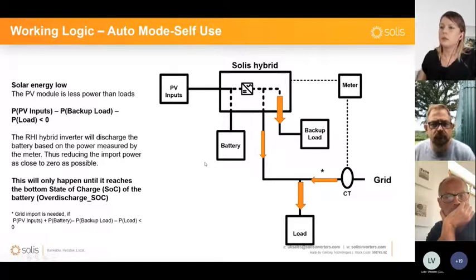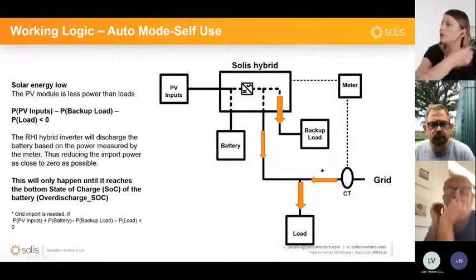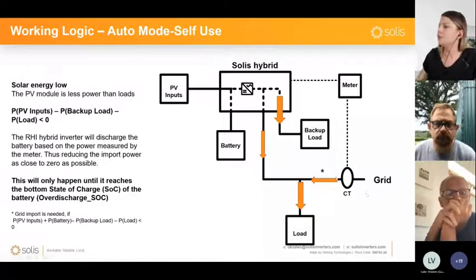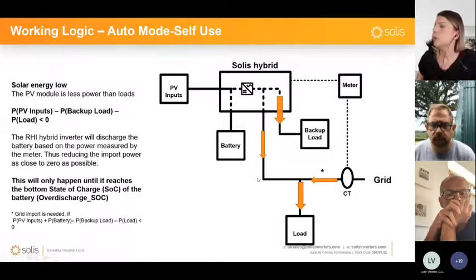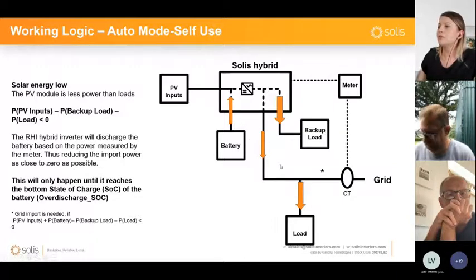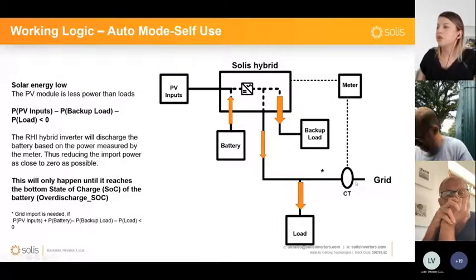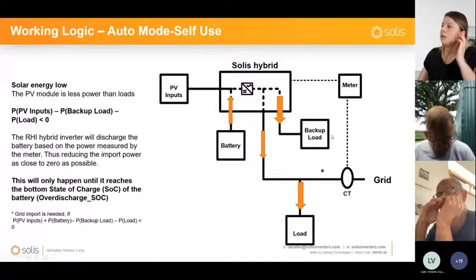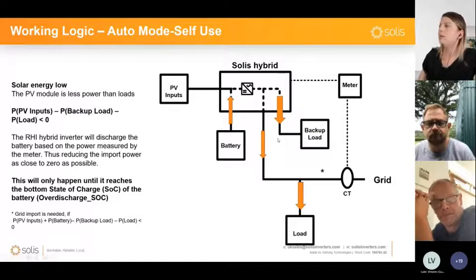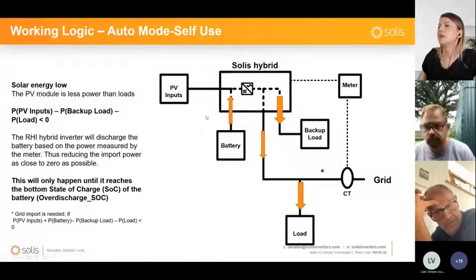So again, as I was mentioning, when the solar energy is low, this auto mode will control the hybrid in such a way that, instead of drawing power from the grid in order to supply the loads, it will start discharging the batteries and lower that grid consumption. This will be done for both the normal loads, which are connected to the main AC port, and the backup loads. As I mentioned earlier, these are being fed through the inverter from the AC side, no matter if PV or battery are available or not.